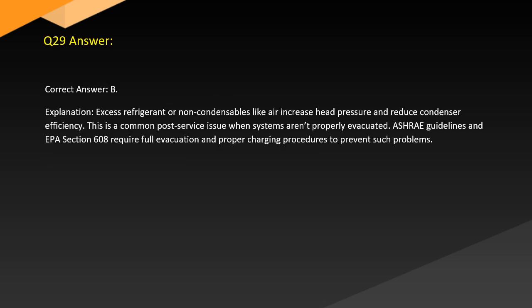Answer. Correct answer B. Explanation. Excess refrigerant or non-condensables like air increase head pressure and reduce condenser efficiency. This is a common post-service issue when systems aren't properly evacuated. ASHRAE guidelines and EPA Section 608 require full evacuation and proper charging procedures to prevent such problems.